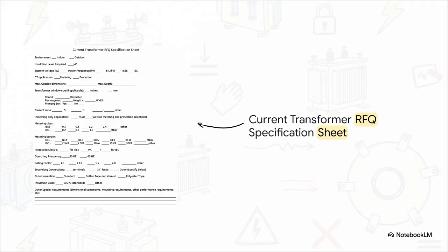And this brilliantly illustrates why we've been going through all this theory in the first place. When you look at a standard request for quote specification sheet, everything we just covered, the primary and secondary current ratios, the metering burdens like B.1 or B.5, the protection classes like C for IEEE, they directly map to the boxes you need to check off. Understanding the background theory directly helps you confidently fill out an RFQ spec sheet so you get exactly the right equipment for your system, no guessing required.